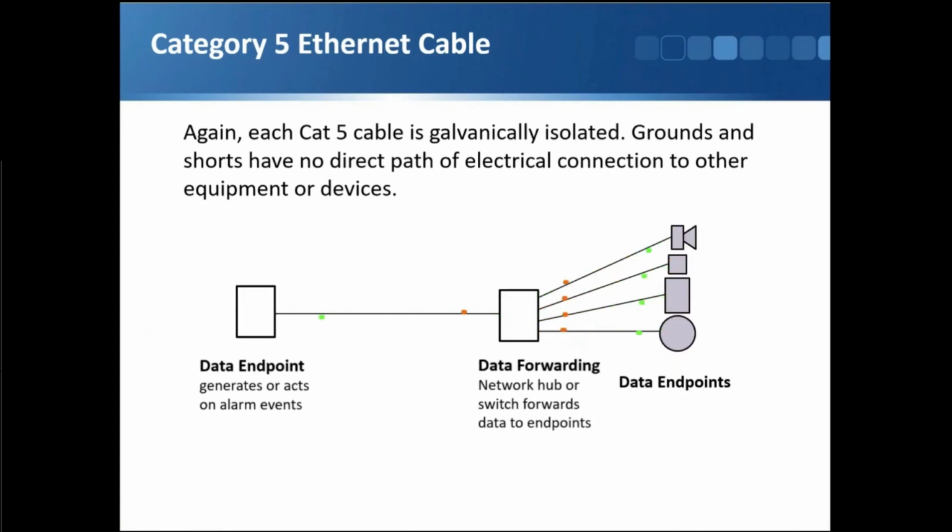So anyway, now we have our packets, and we're traveling across these wires. Packets are going back and forth. At every end of every cable, they're being verified that they're still good, and they're isolated from ground, so we have a good communication. Of course, you could get these 2 grounds here, and nothing happens. It doesn't matter if it's on this other segment, as long as it doesn't short out that same plus and minus.